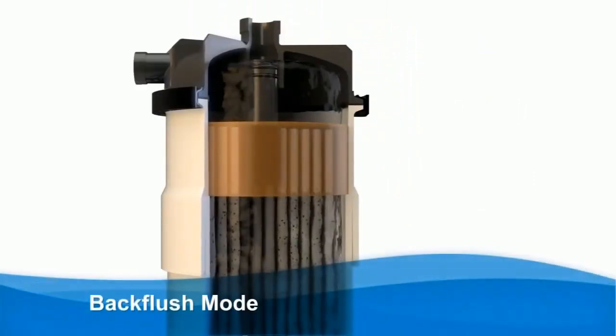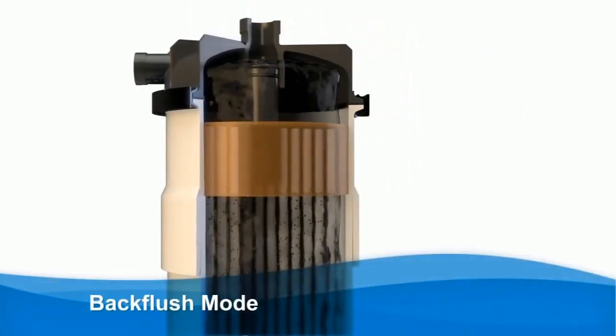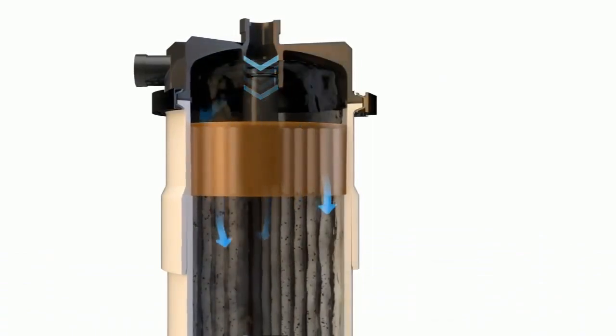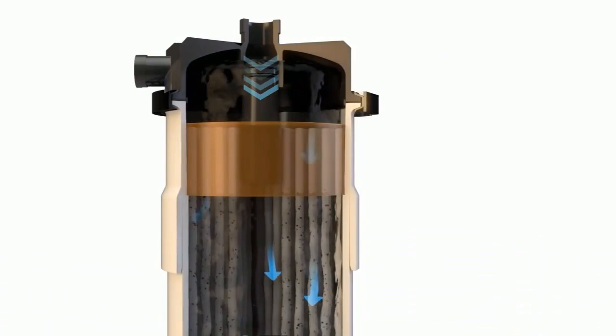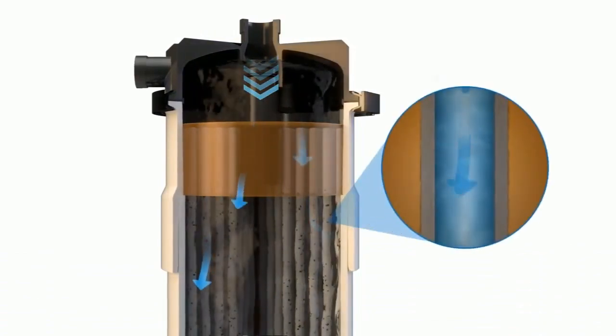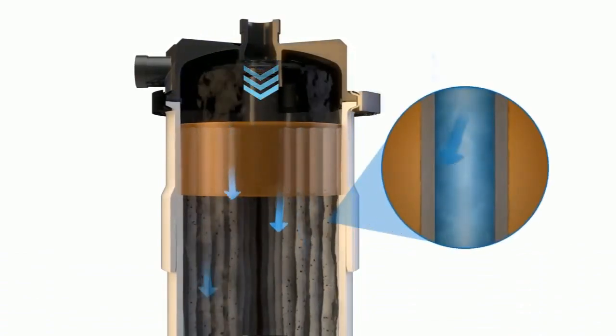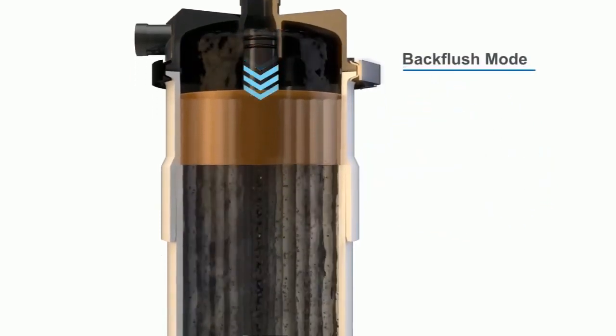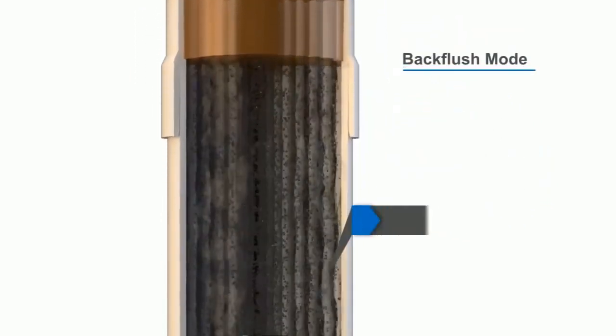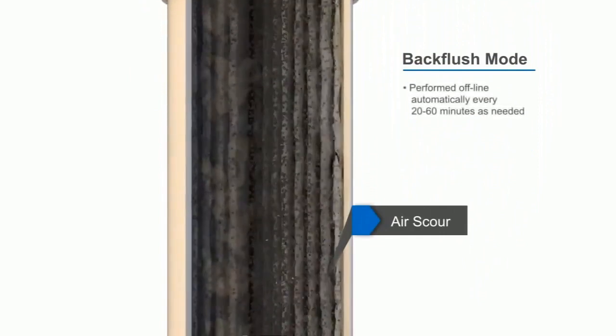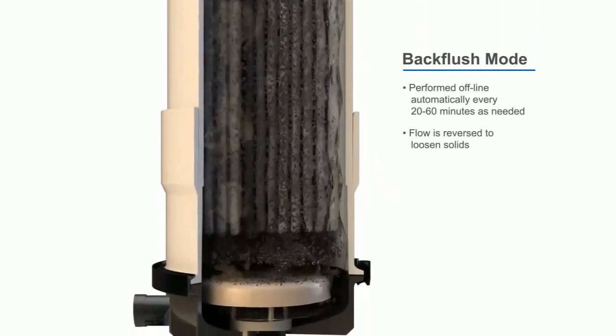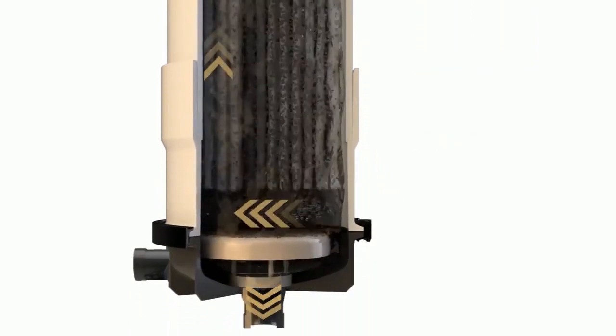Backflush process is very important for productive efficiency. During backwash, filtered water is reversed through the hollow fiber module in an inside-out flow direction. Vigorous air scour simultaneously penetrates the membrane bundle to dislodge accumulated solids from the fiber. The cartridge's open flow design allows nuisance solid particles to go through the backwash drain line.